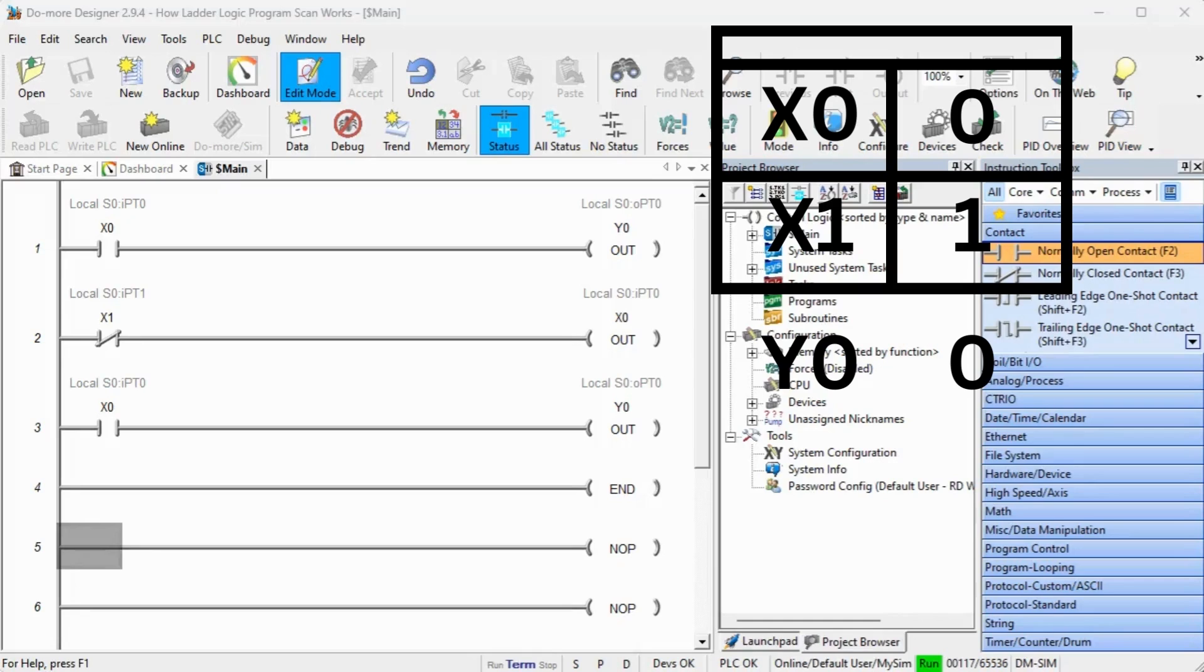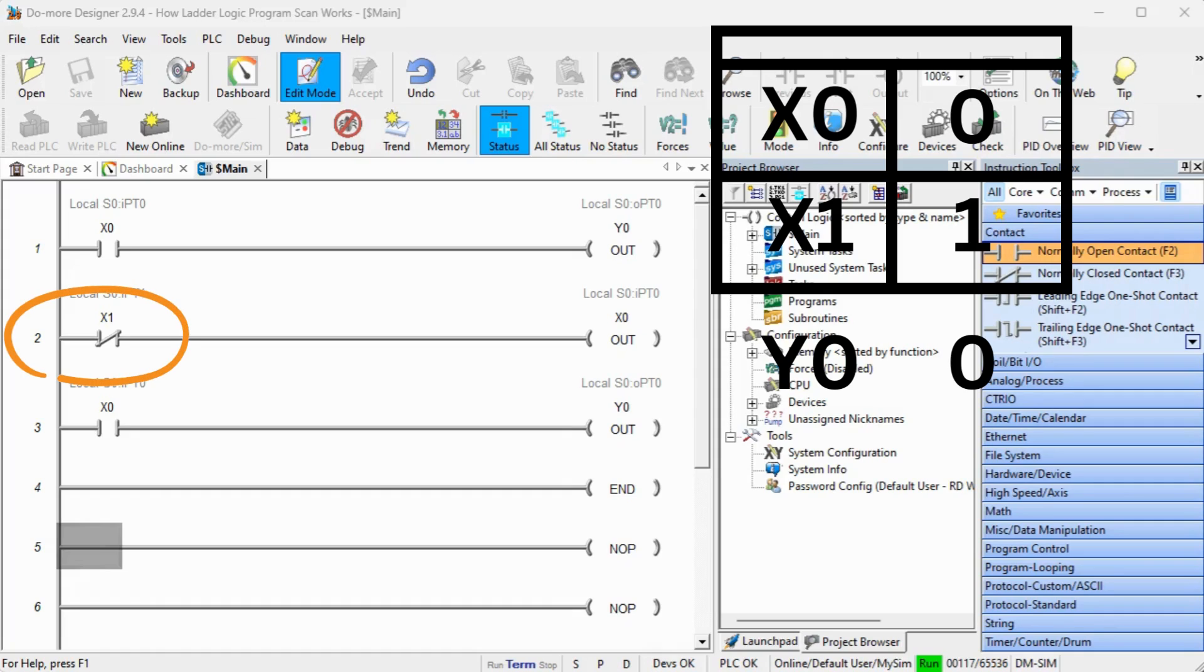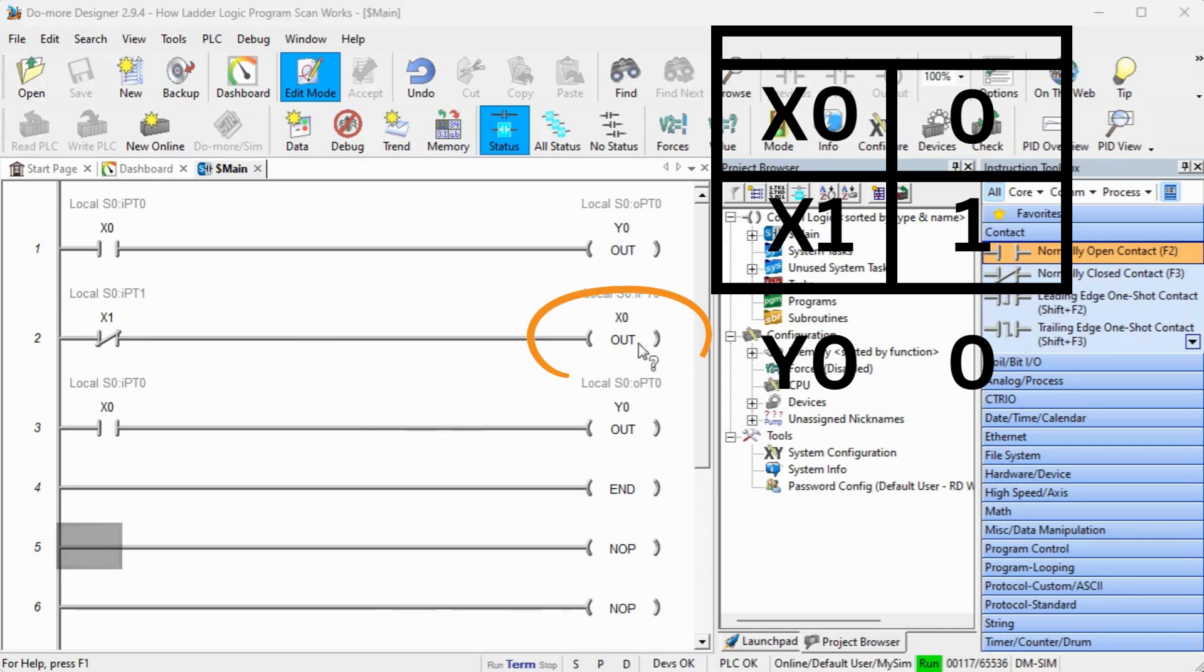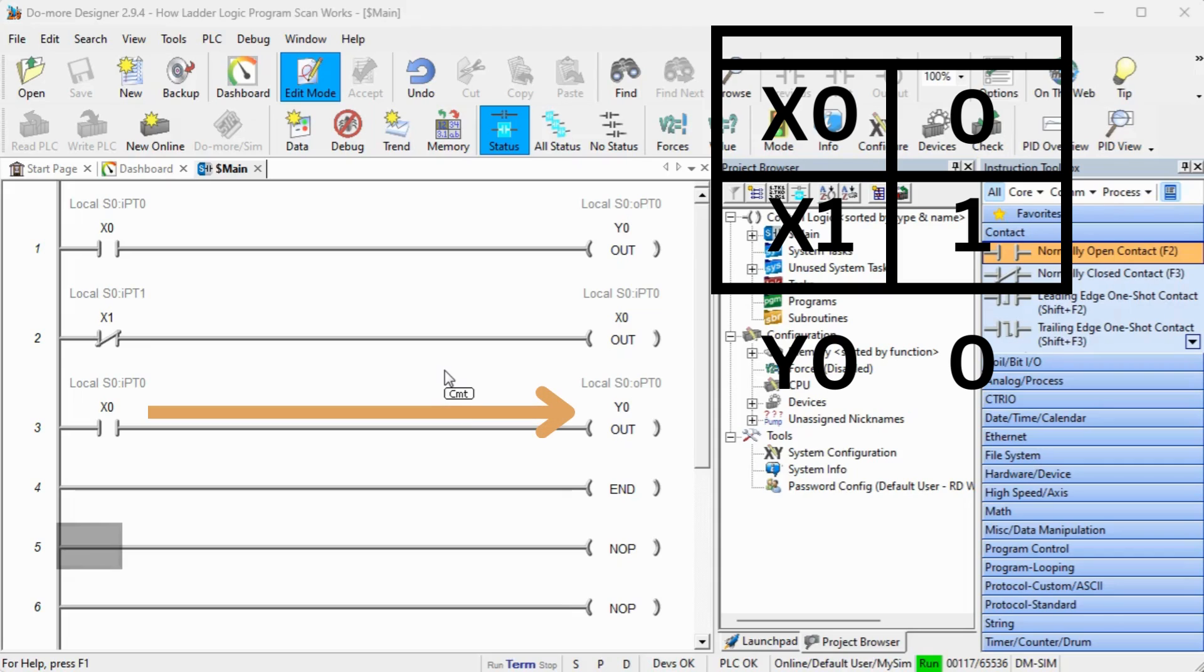We have now added a couple more rungs to our existing program. This will demonstrate the execution of the program. The normally closed x1 input will now set the output x0 in the memory table. The status of x0 will now control the output status of y0 in the memory table. Rung 1 is repeated as rung 3.